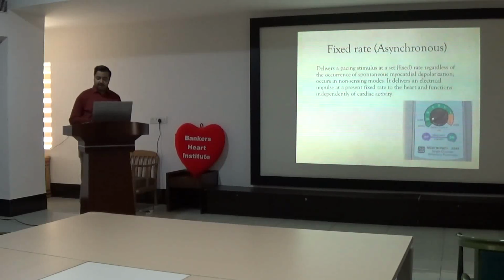Third would be when you are at home at night and suddenly somebody calls that the pacemaker is not pacing. At that time you increase the heart rate to 100, turn the output up to 10 or more than 10, and go to asynchronous mode. If it is pacing in asynchronous mode, there is something wrong with either the patient's rhythm or the system. If it does not pace in asynchronous mode also, the lead has been disturbed. Then you need to reposition. So just to look whether the problem is with the pacemaker, the lead or some other problem, asynchronous mode can be tried.